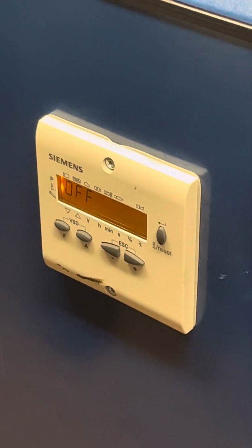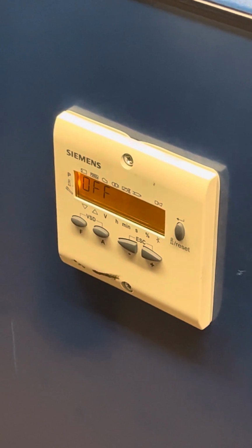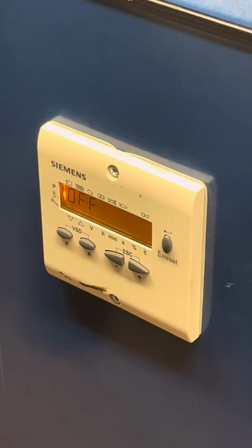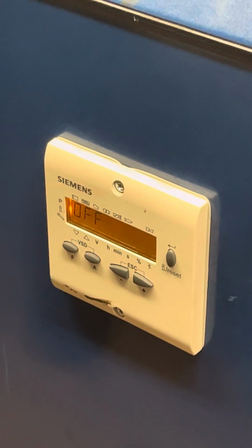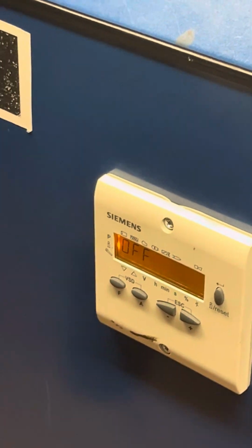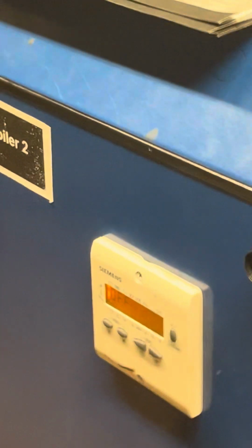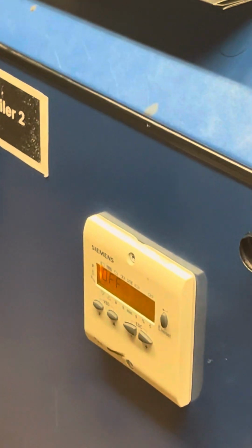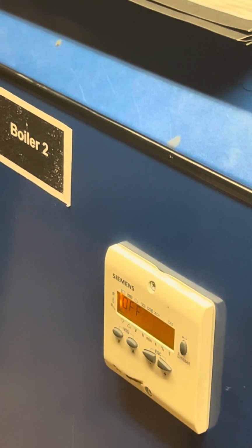Yeah, as soon as you log in, the first option it gives you is to adjust combustion, and as soon as you touch something and do it the wrong way, it's going to lock out the burner. It's going to go off unprogrammed, and then a technician has to come in and reprogram the control. So don't go in there unless you need to, but it's training, so I want to give you whatever information you need.